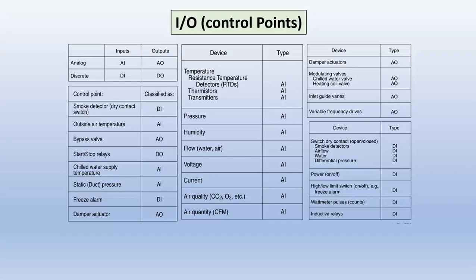Now the analog input and output, anything that moves that you need position indication of, those are good examples of analog input or output. Let's say a temperature or say I want to move a duct or a damper. I want to modulate it. If it's modulating, it needs to be an analog output. Let's see, here's some examples of some analog inputs. Air, or CFM for air quantity, CO2, current, voltage, flow, any type of parameter that changes that is not just on or off, you're going to need an analog input for.